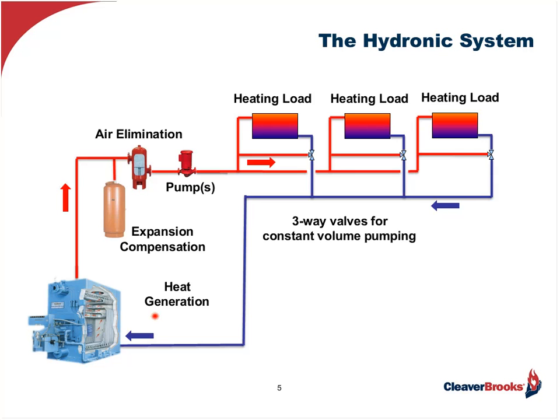There's an air elimination device. This is your air separator, typically. It will have an air vent. We want to remove entrained air from the system. Air that's entrained will ultimately come out of solution of the water, and this will cause corrosion, scale, which will cause your efficiency to decrease, as well as even blocking flow if it's not vented properly. So that's an important part.